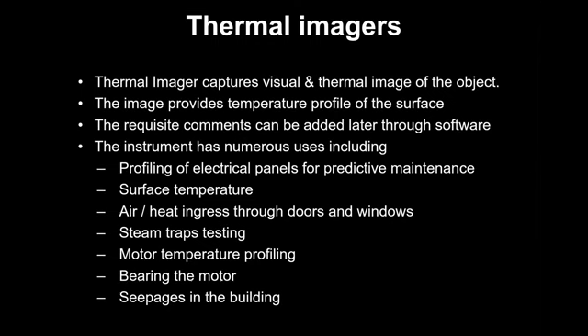Thermal imager is another extensively used instrument. Ashok already spoke about it. Now it captures visual and thermal image. That's the advantage. You know, you have a visual image also, so that you know how it looks normally and how the thermal profile of that image looks. So based on that, you can identify the locations where the temperature is on the higher side. It'll give a complete profile of the surface. Unlike infrared, you know, infrared will give you a point value. It will give you the temperature of the entire surface in an image form. So you can correlate, you can analyze it later.